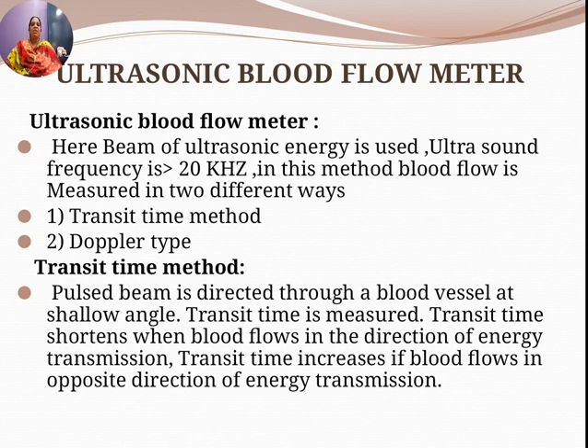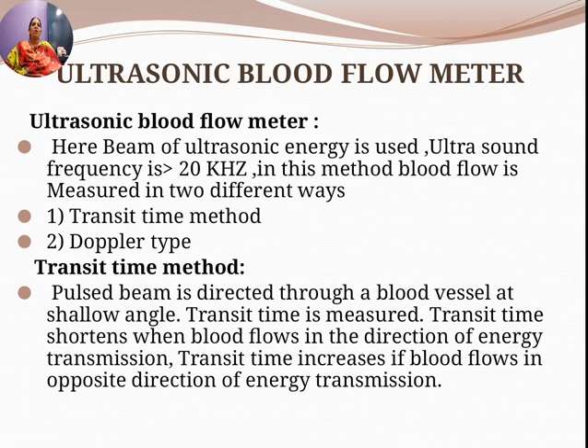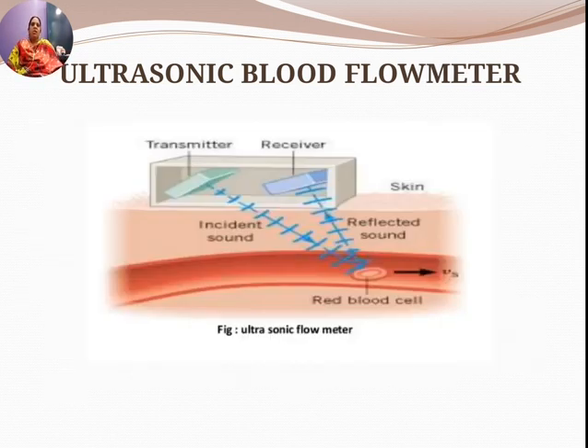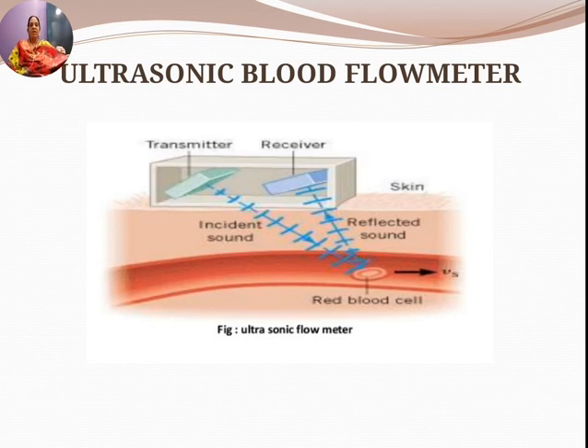In the transit time method, a pulsed beam is directed through a blood vessel at a shallow angle and the transit time is measured. Transit time shortens when blood flows in the direction of energy transmission, and increases when blood flows in the opposite direction. So from the diagram, sound produced by the transmitter passes through the blood vessel and is reflected back to the receiver.